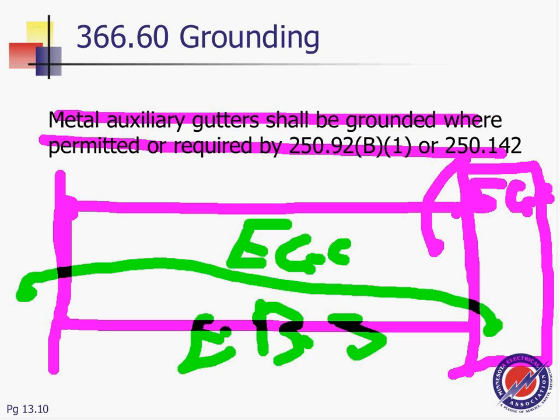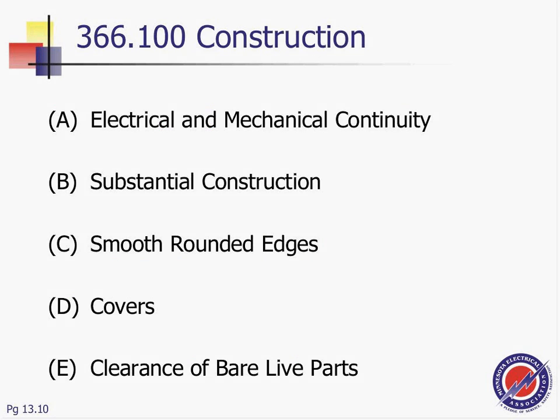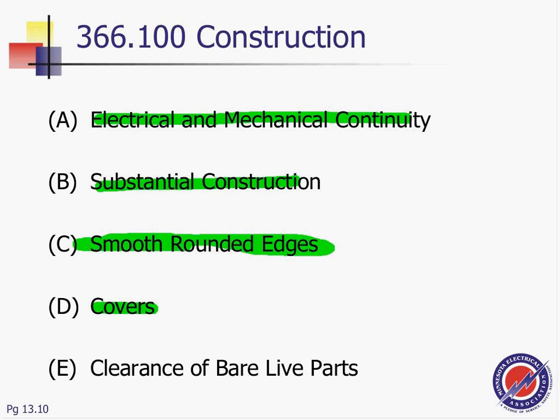If it's metallic, it has to be securely fastened on both sides, electrically and mechanically connected, so as to provide a grounding conductor. Construction, again: electrical and mechanical continuity. It has to be substantial construction, made of material with smooth edges, no rough edges. We don't want to damage the conductor. Covers, and clearance of live parts.